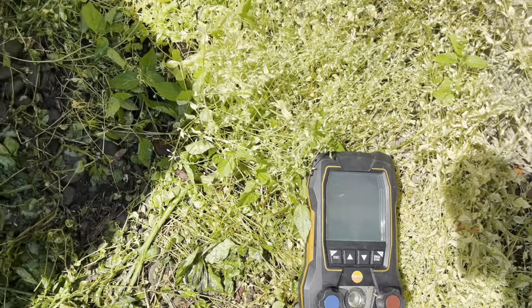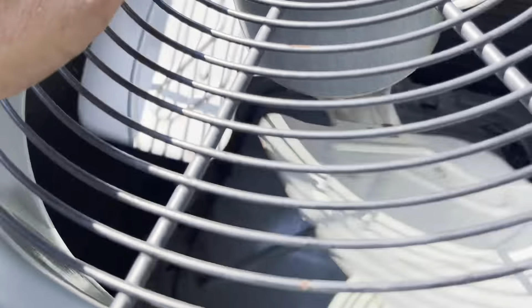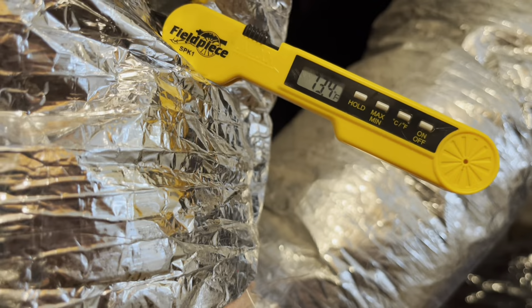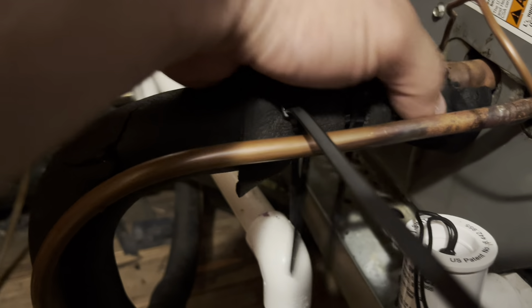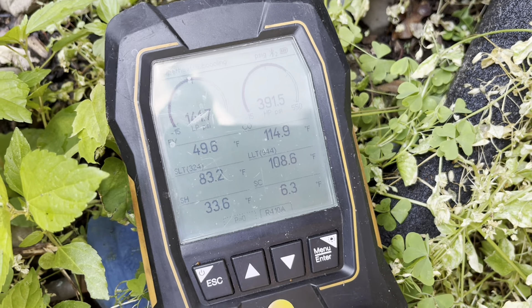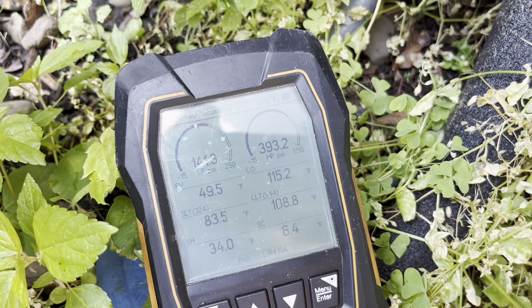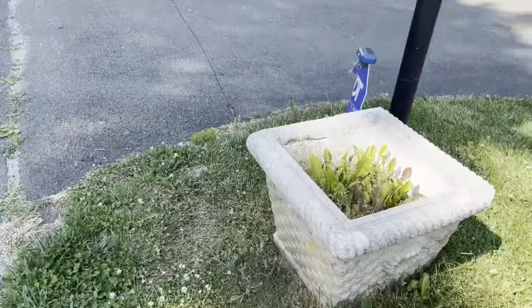Look at them apples — 38. We'll go check temp split. Sounds a lot better, it's not running like crazy hot. Zip tie the heck out of this. I put some insulation tape on it for good measure. I'm going to cut these and go check my pressure again. I added one pound six ounces of 410A so far. We're still low. It took two pounds three ounces. The factory charge is 70 ounces, which is 4.375 pounds. Now I'm just going to check — it's 87 degrees in there.